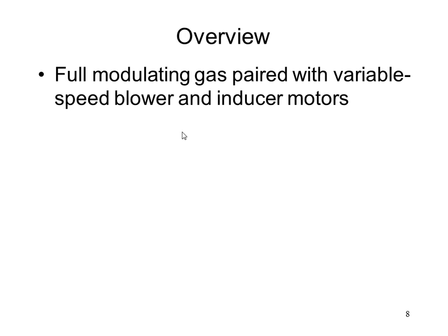Like we said, the modulating gas valve itself is paired with a variable speed blower and a variable speed inducer. All three of these things are going to vary at the same time, and that's one of the reasons that we use the communicating control on this: a regular thermostat wouldn't have the ability to convey its needs to the furnace to let it know how much to ramp these things up and down. So the furnace is going to get data from the communicating stat on the wall, which is basically going to be what's your temperature and what's your set point. He's going to figure out how far you are from set point and how fast you're getting there, and he's going to modulate all these things in conjunction with each other.